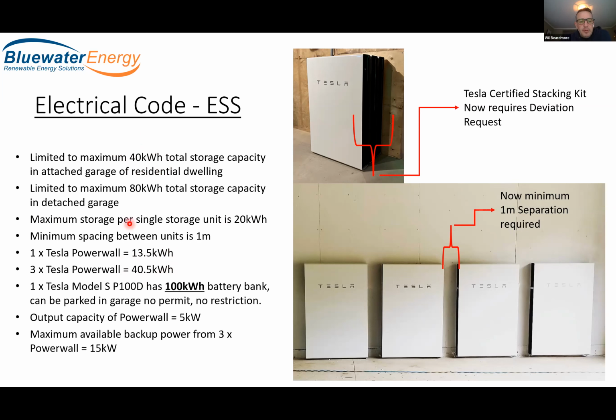Because of this maximum storage per single storage unit of 20 kilowatt hours, when we stack two Powerwalls together, and up here is a picture of three Powerwalls stacked together to save space, using an approved certified stacking kit by Tesla that has been tested and fire rated, ESA says we've now taken two 13.5 kilowatt hour units and made them one. Now we're at 27 kilowatt hours, which is greater than 20, which means we can't do this.